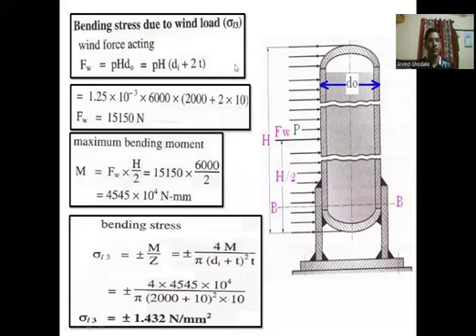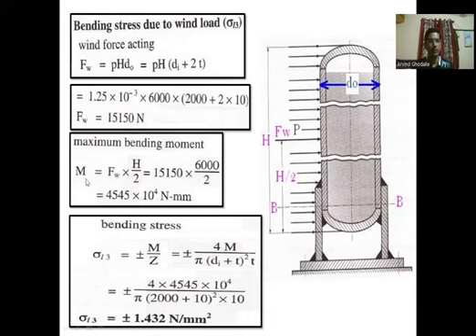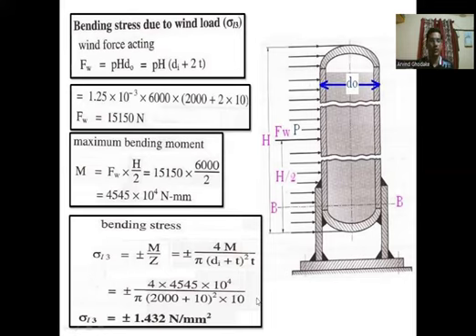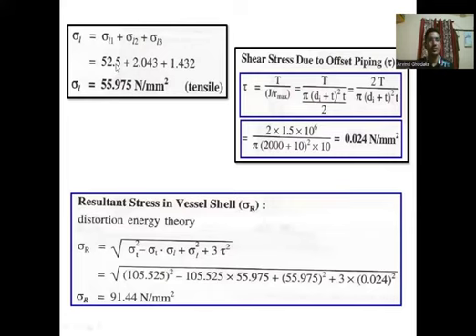For bending stress due to wind load: wind force FW = wind pressure × H × (DI + 2T) = 15,150 N. Maximum bending moment M = FW × H/2 = 4545 × 10⁴ N·mm. Bending stress sigma_L3 = ±4M / (π × (DI + T)² × T) = ±1.432 N/mm². Therefore, resultant longitudinal stress sigma_L = sigma_L1 + sigma_L2 + sigma_L3 = 55.975 N/mm².